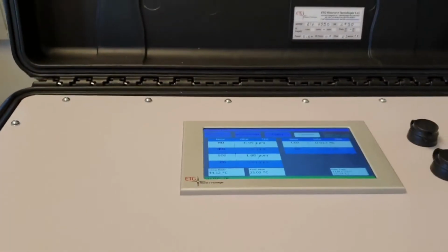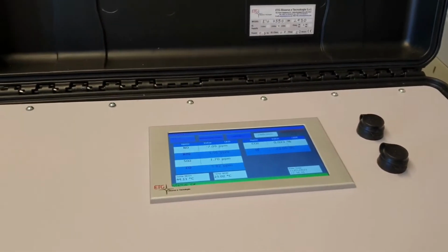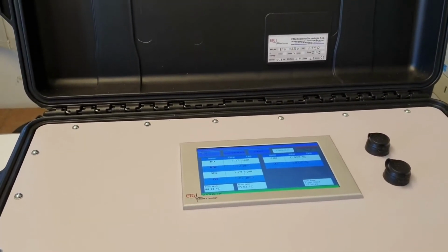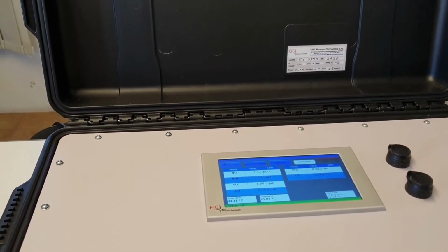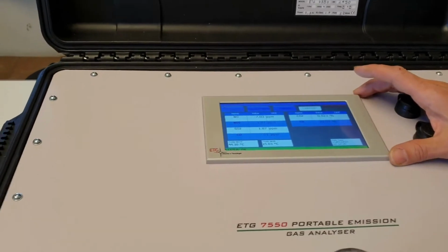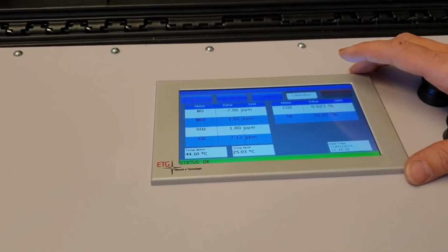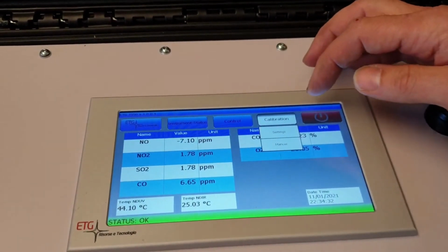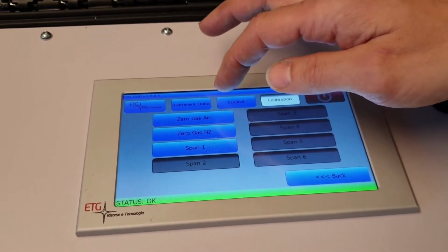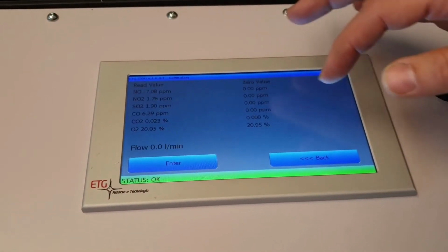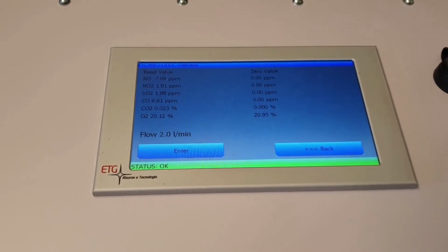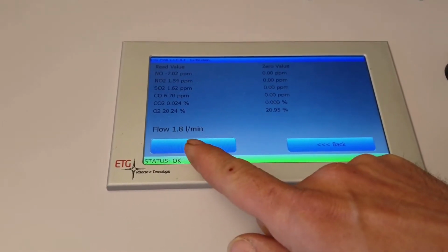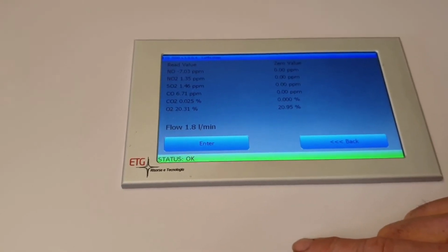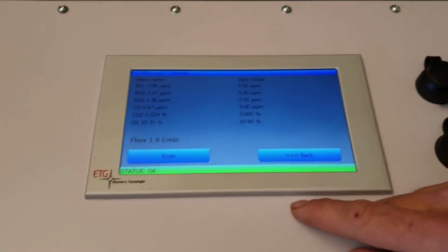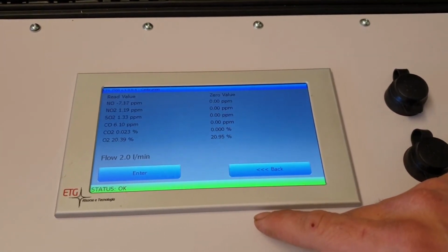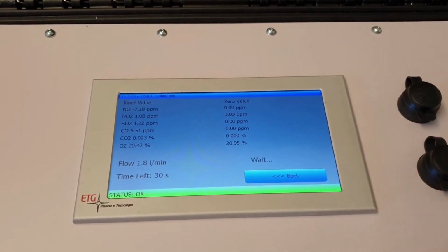Okay, now before starting the sampling we suggest doing a zero calibration of the analyzer. To do the zero calibration, it's necessary to proceed this way. Go to the calibration menu, manual, zero gas air. You can see the flow of air that goes through the analyzer. And push enter to start the procedure.